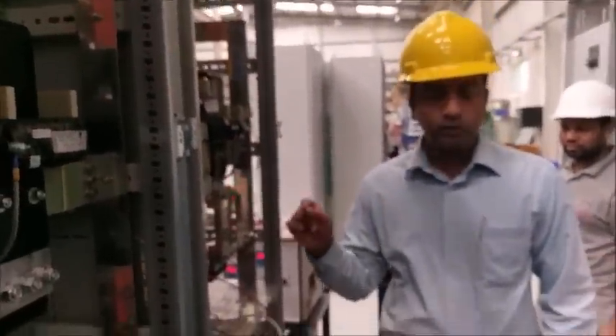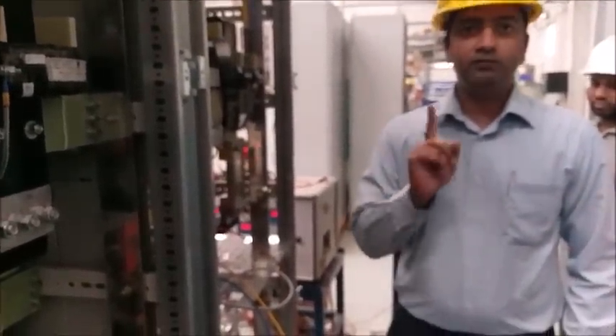Now this is the Megger test for the dielectric. Shall I connect it right now? Shall I do the test? Sure. We need to do the high voltage test. So what we are doing is giving 2500 volts for 1 minute.